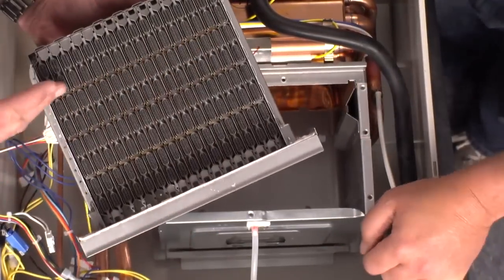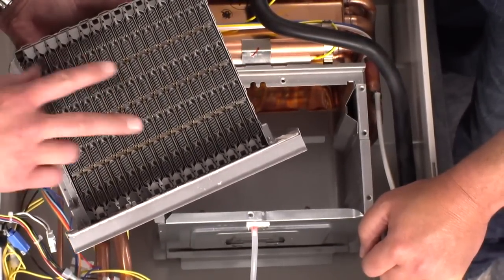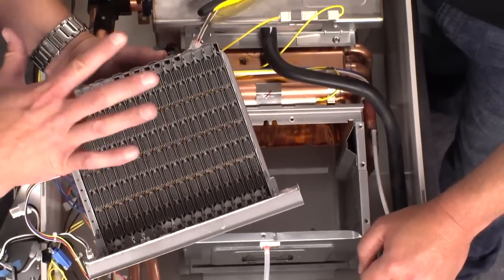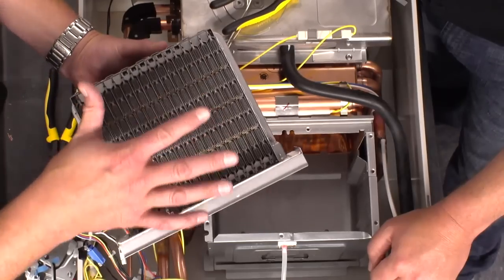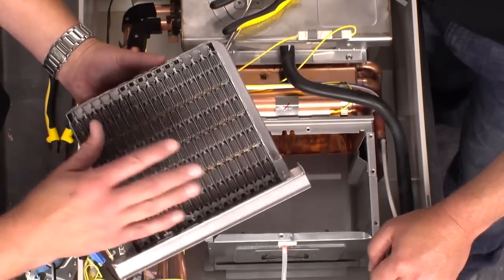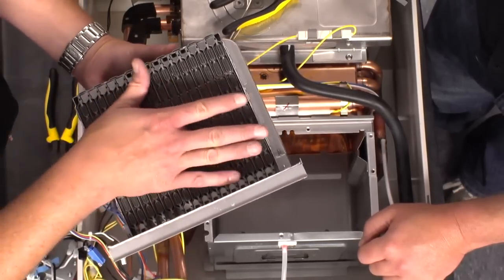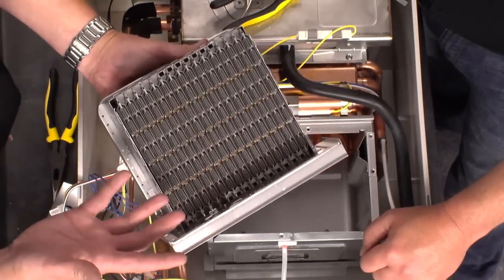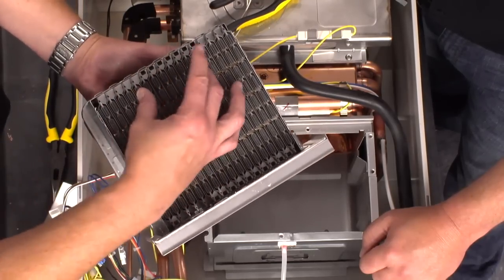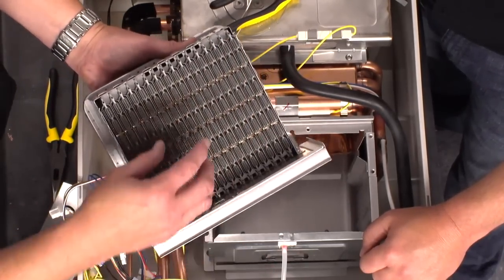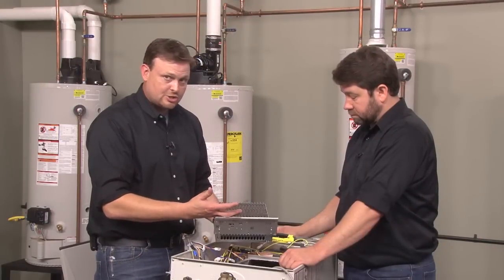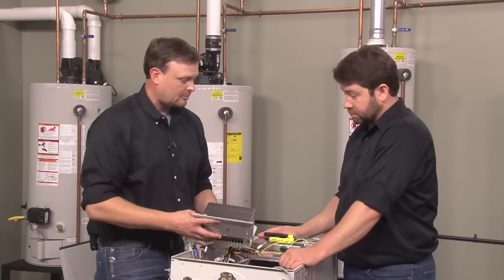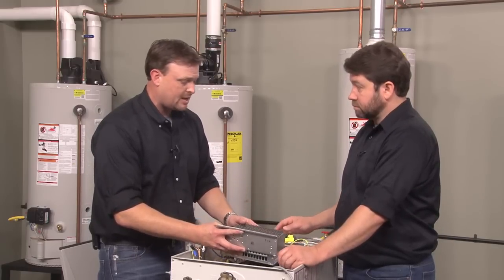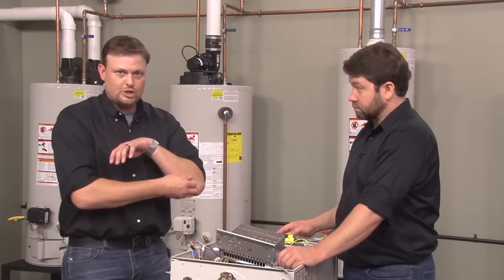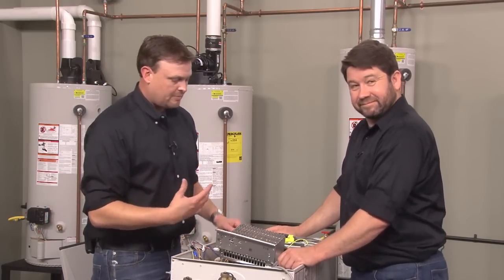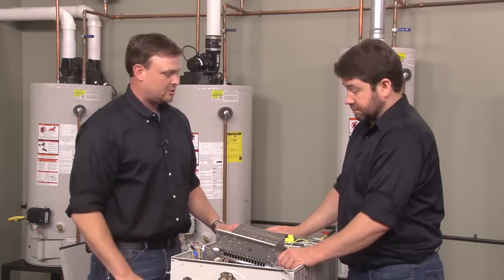Now you look at the burner. It's got 16 individual stainless steel burner plates. Again, when we're servicing this, we can use a degreaser. You know, you can use water. You can clean it out, compressed air, whatever you got to do to get it cleaned out. And then you're inspecting it. You're going to look for any discoloration or some condensation, maybe an issue. You can look for any damage to the burner because of condensation. And then we know we've got a problem maybe with the trap or something like that. But it's a good idea when you do service the water heater that you pull the burner out, take a look at it, make sure it's working properly.